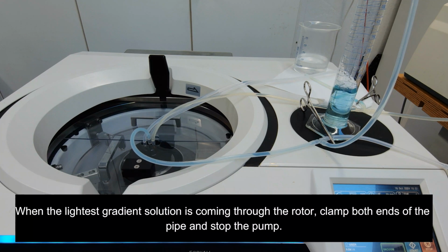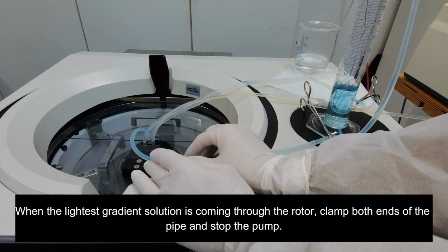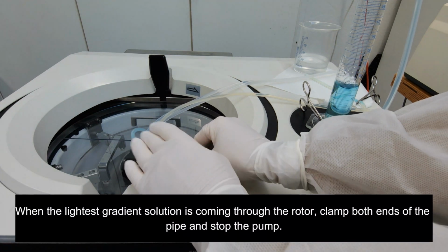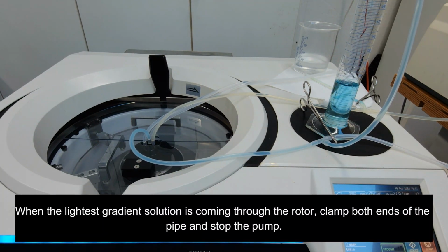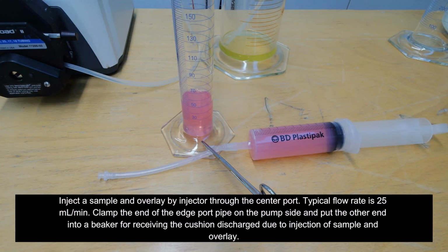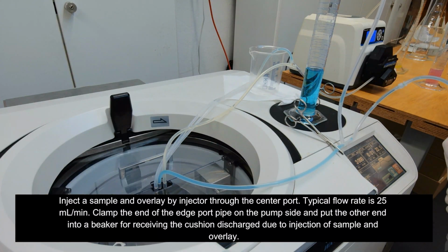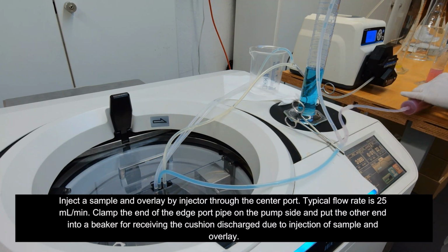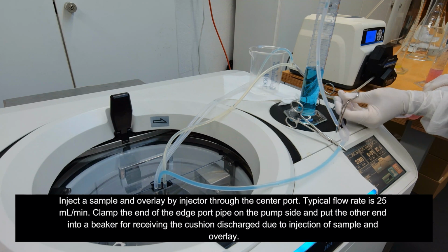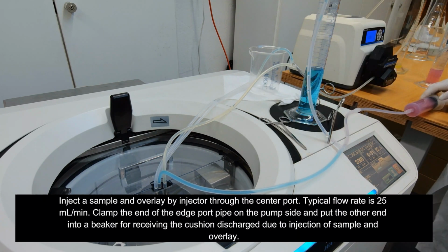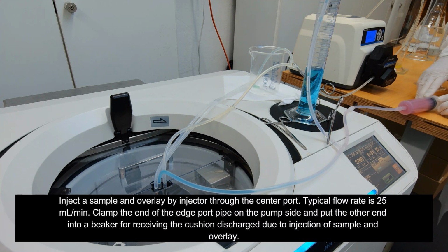When the lightest gradient solution is coming through the rotor, clamp both ends of the pipe and stop the pump. Inject a sample and overlay by injector through the center port. Typical flow rate is 25 milliliters per minute. Clamp the end of the edge port pipe on the pump side and put the other end into a beaker for receiving the cushion discharge due to injection of sample and overlay.